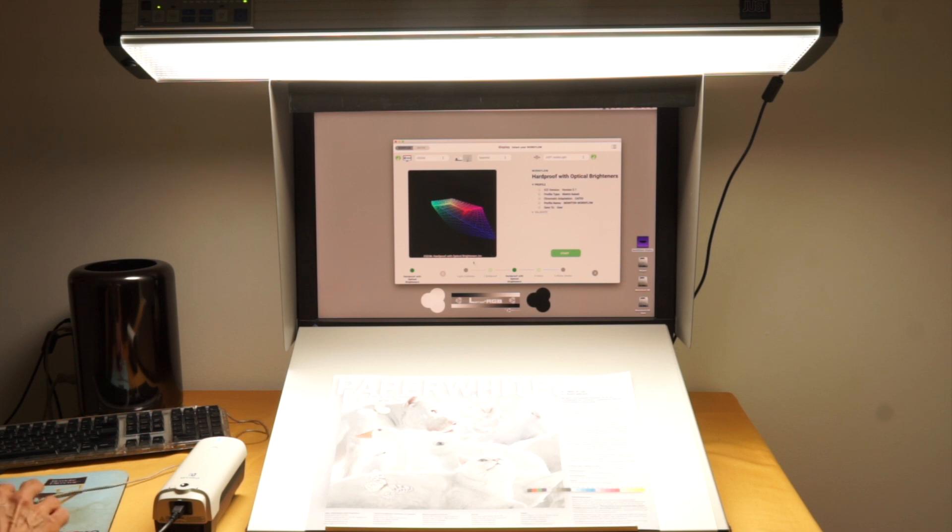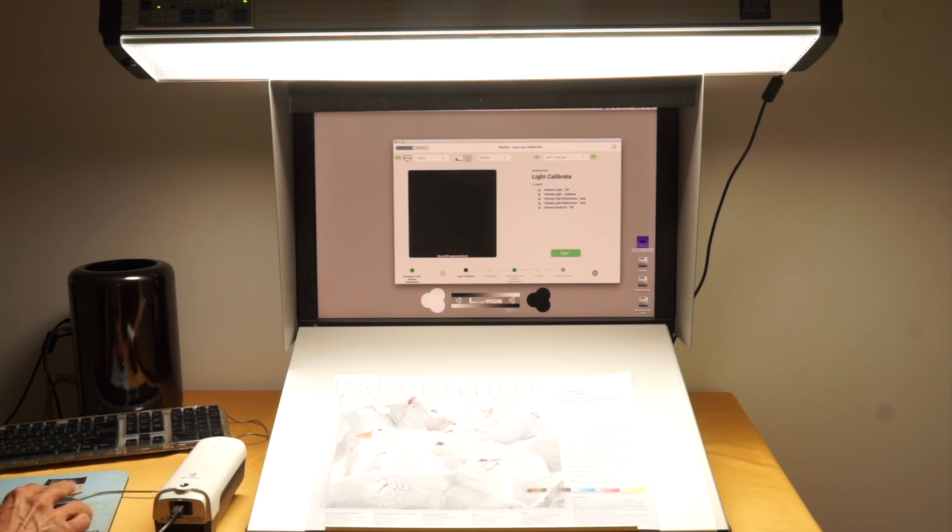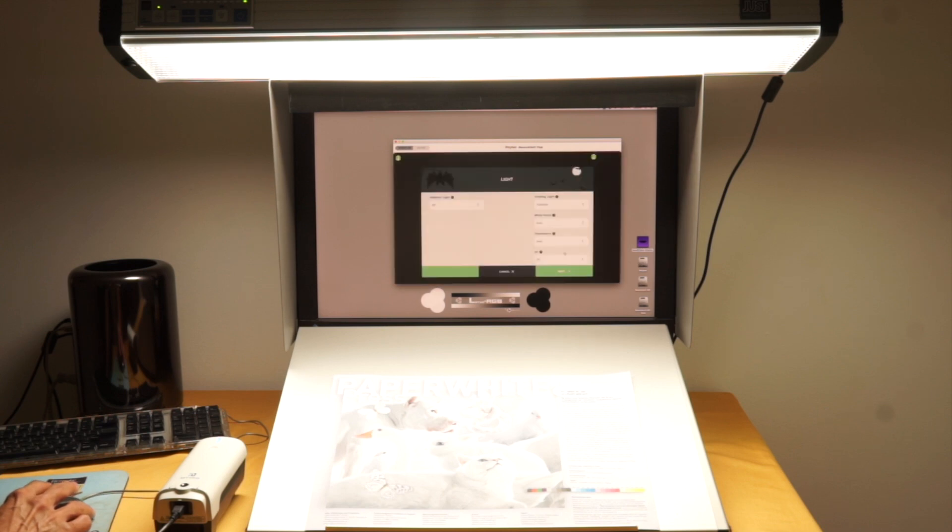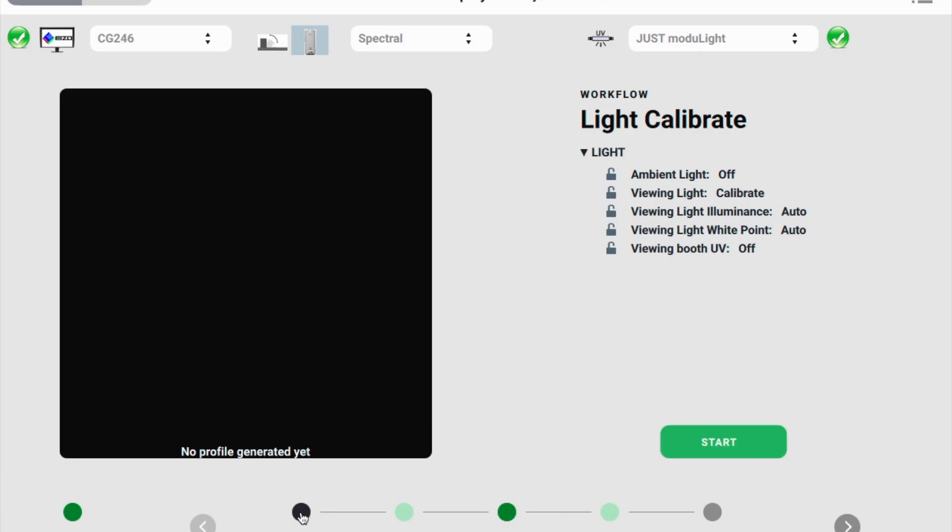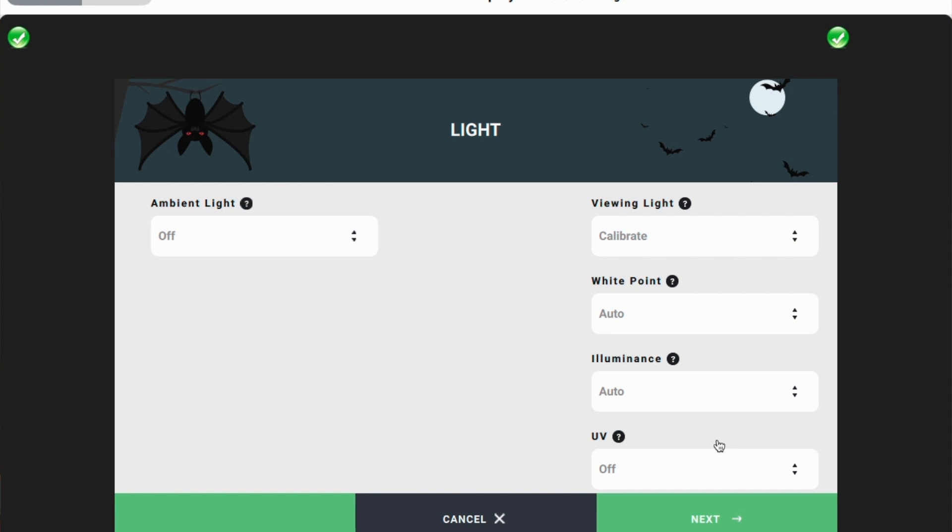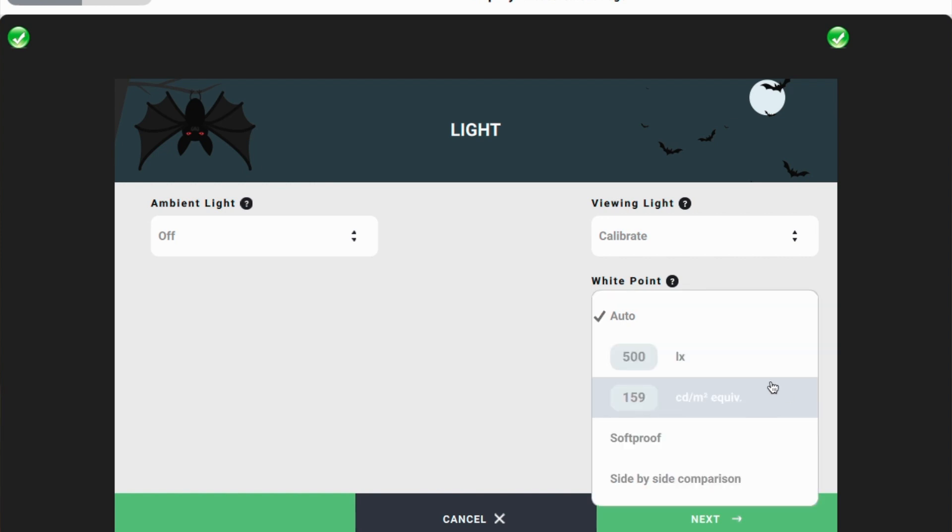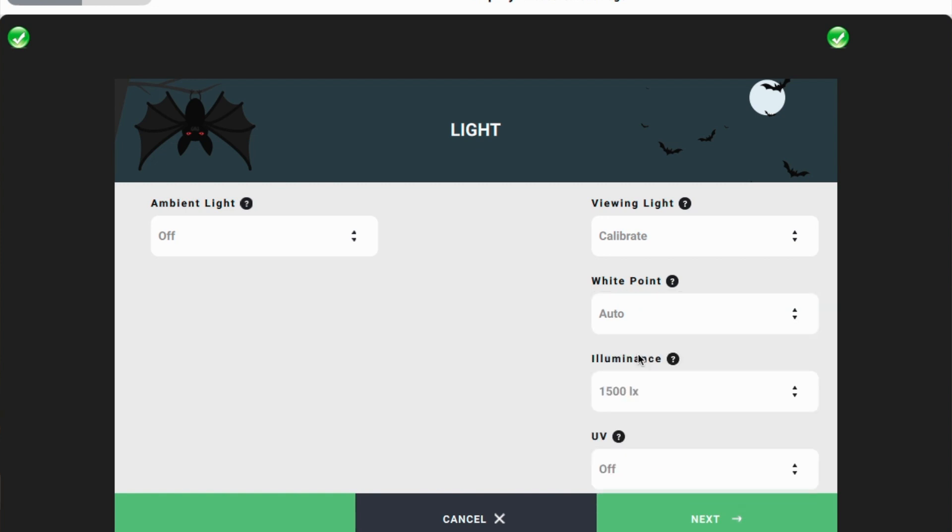So I'm going to demonstrate now how I actually calibrated this. I have a light calibration here. Start. I can check ambient light, viewing light, and say I want to calibrate. And for the illuminance I'm going to put my 1500 lux in. And here I can say I would like to do this with UV on.